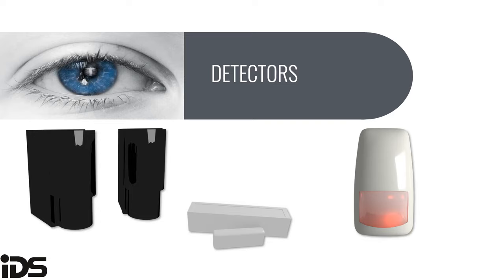When the magnet gets close — for example, the door closes — it pulls the two metal plates together, closing the circuit. This is why door contacts are normally closed devices; when the door is closed, the circuit is closed. A tip: the closer the door contact is installed to the hinge, the more the door can be opened before the contact activates. So if a client wants to keep a window slightly open, install the contact closer to the hinge to allow a wider opening before triggering.